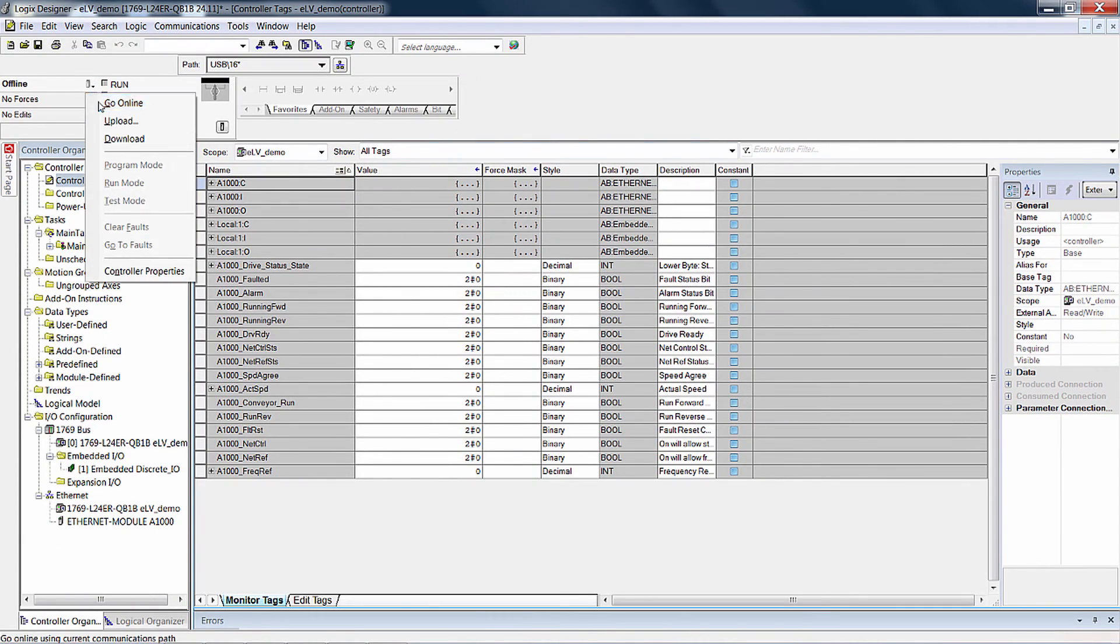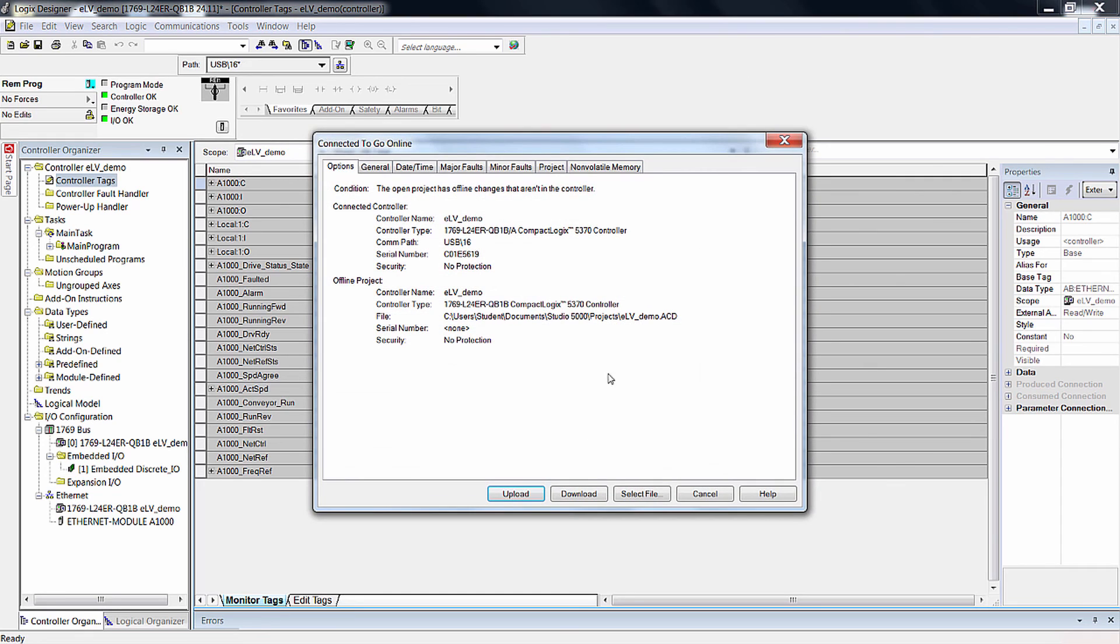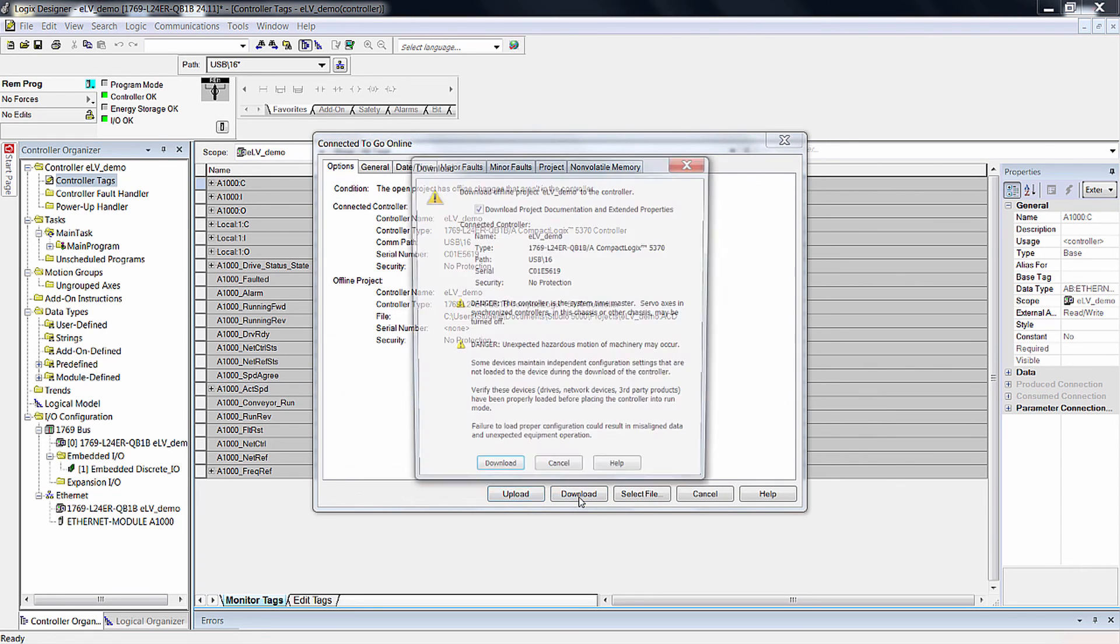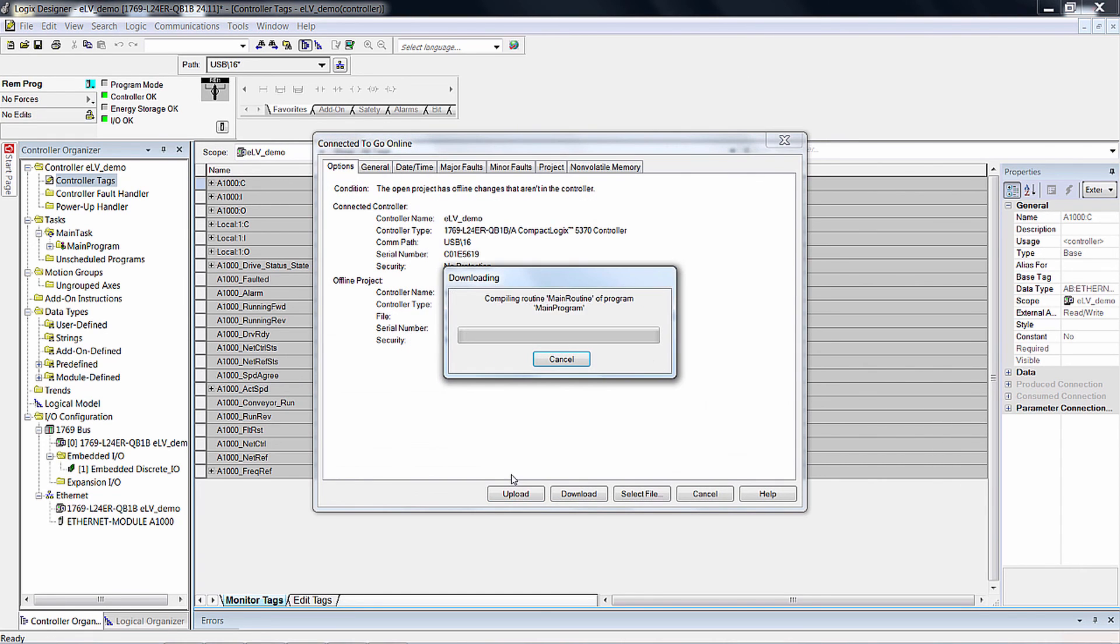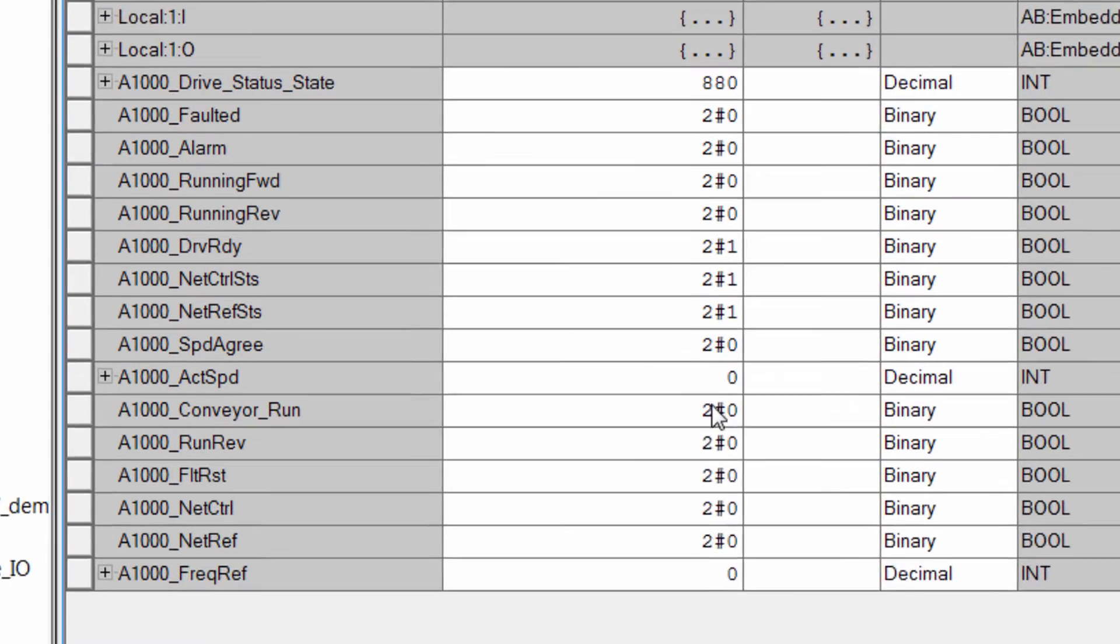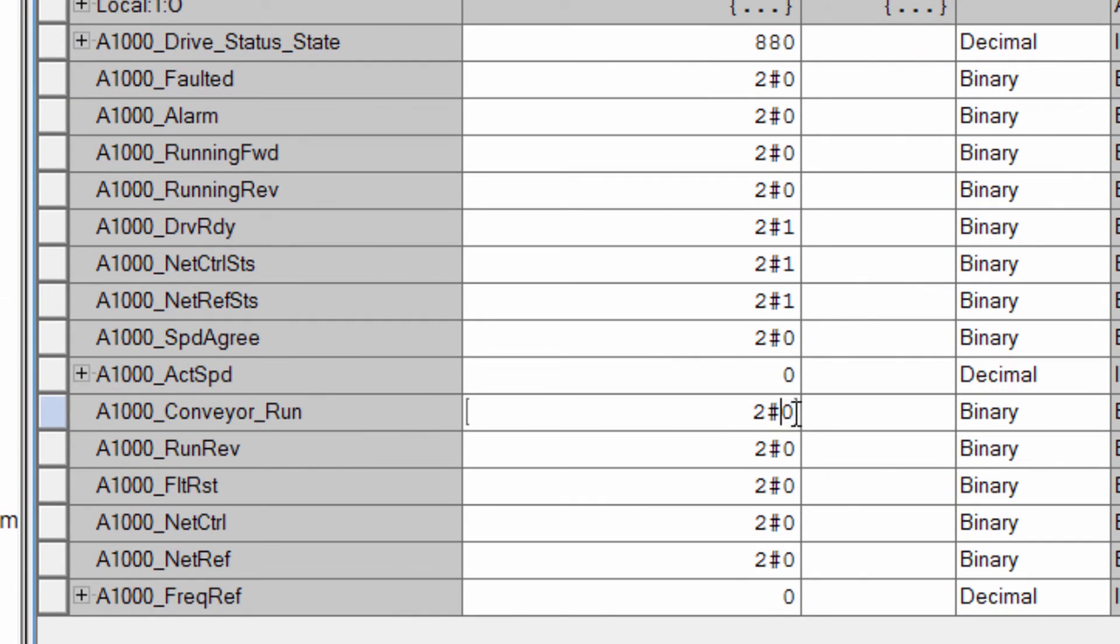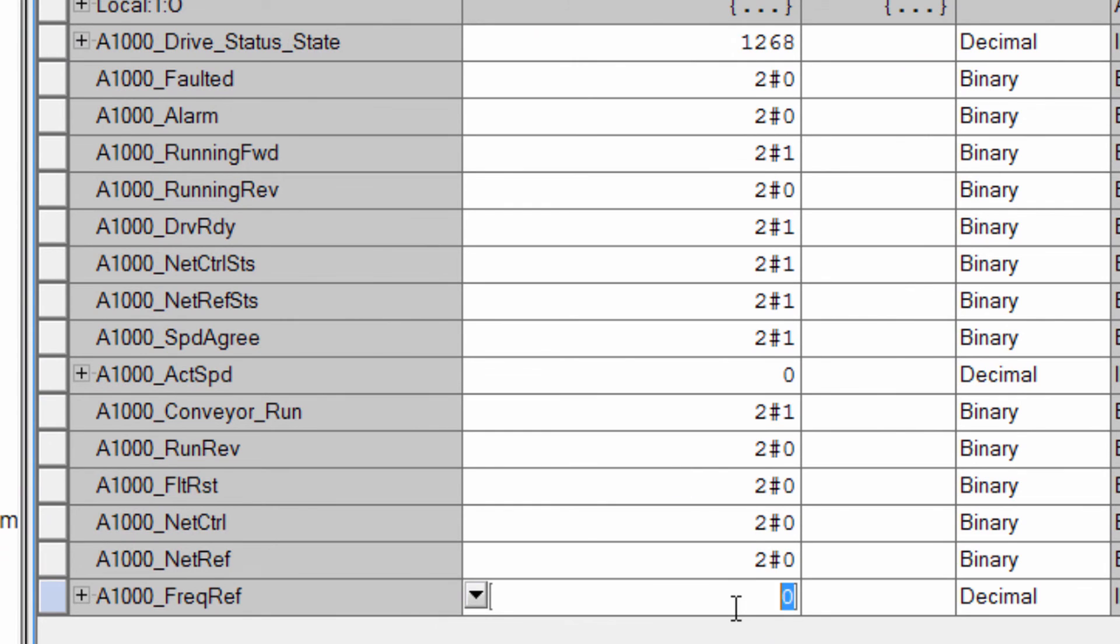Once we are online, we can test tags by using them to run the VFD. We'll demonstrate that here by setting the Conveyor Run to 1 and entering a 45 Hz frequency reference. Then we can verify that our motor indeed responds.